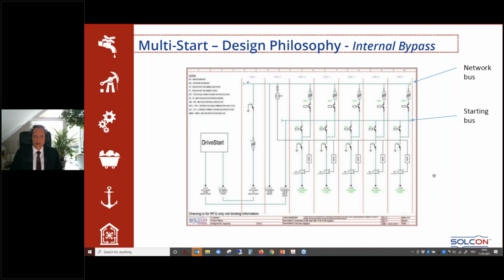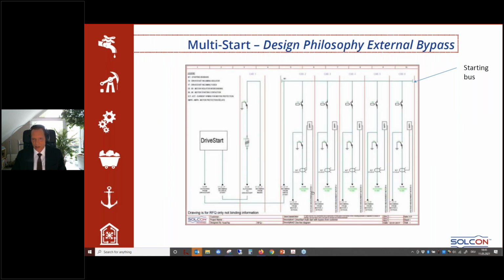What is our design philosophy when it comes to the topology? You have here the drive start, you have here the incoming. This is the so-called network bus. You go on here. Here's a separator switch. You go into the drive start, into the IGBT portion. Here's the variable frequency, and here you have the startup bus. And you can start consecutively motor after motor with these bypasses. Or in some cases, customers prefer to have the bypass on their own. That means you are connecting each motor with the external bypass coming from the customer.